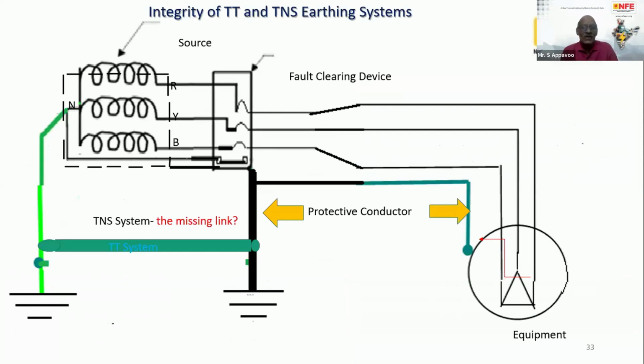Okay. So now I am coming to the subject, slightly touching it. I am just giving the missing part that we usually do not take into account during our execution, design, as well as verification. So this is a typical TT-TNS system. We call that we are having a TT system. The difference is there is a link between the protective equipment conductor, because it is the source, the overcurrent protective device, the conductor, and the equipment. If there is a fault, that will flow through the protective earthing conductor and through this link.